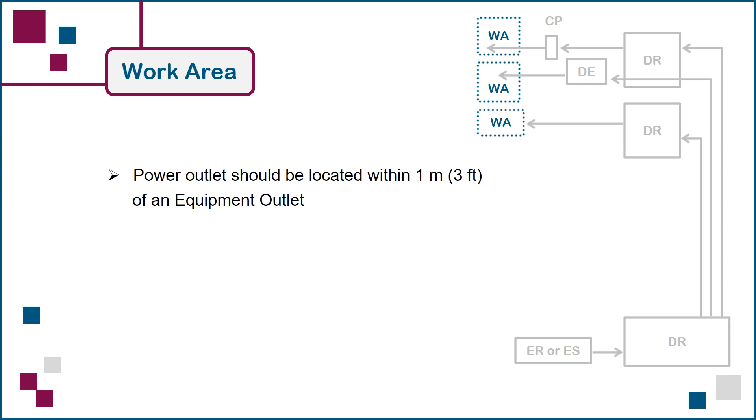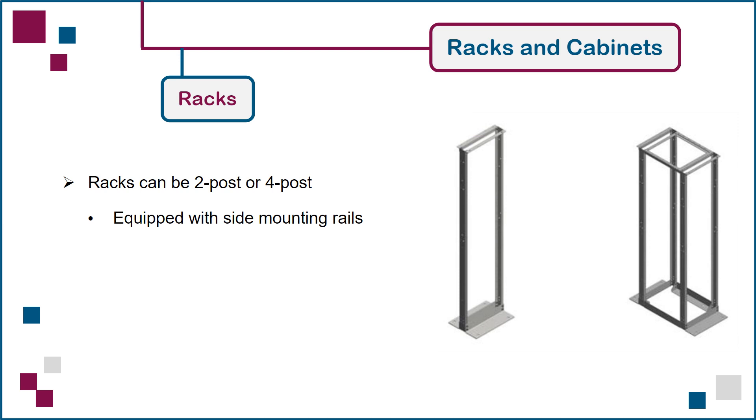This concludes the review of telecommunications spaces within commercial buildings. Next, we look at spaces in the form of racks and cabinets, which are commonly located in distributor rooms. Racks and cabinets can be described as movable telecommunications spaces, since they house both network equipment and cable terminations. Equipment racks are basic units consisting of two or four posts. Since all sides are open, there is no way of controlling airflow through a rack.